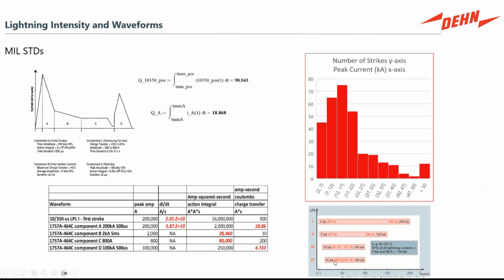If you have higher risk, you need to pay attention to more of the spectrum of lightning strokes. So the high risk category, LPL1, pays attention to what I would say is the full 99% of any strike that's going to happen, high or low. And if you have less risk, say a typical industrial LPL3, you are certainly paying attention to more than 90% of the lightning strikes, the who's who in the zoo of what the strike might be. But really, it's about paying attention to the low level strikes that provoke that small rolling sphere. That's where the highest risk can then be protected.